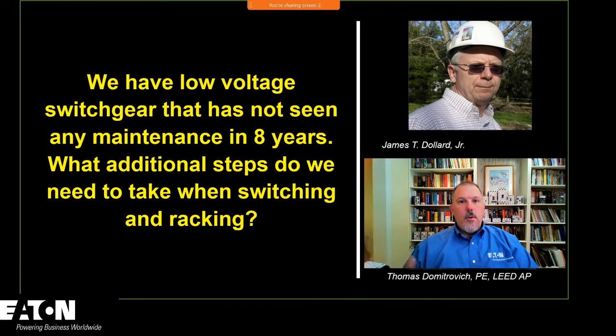So you had that going on. You had 240.87 and 240.67, the discussions around 1200 amps and above, which, in many cases, is going to be up there close to the utility, close to your service entrance equipment, or be your service entrance equipment. And then you had the labeling requirements in 110.16(B) that was going on. So you had all of these discussions going on about the hazards and incident energy and all this good stuff.